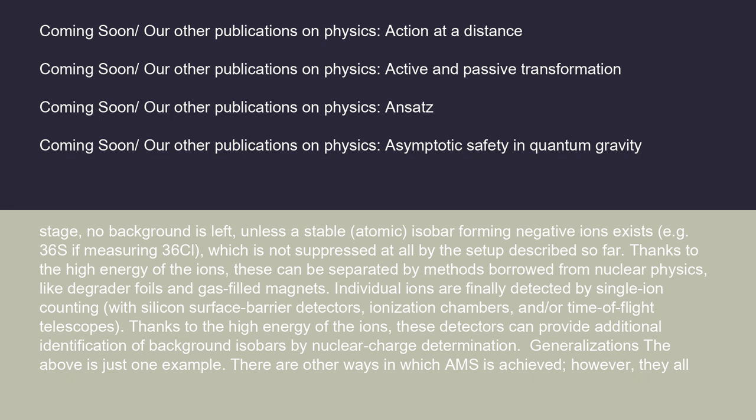After this stage, no background is left unless a stable atomic isobar-forming negative ion exists — e.g. 36S if measuring 36Cl — which is not suppressed at all by the setup described so far. The ions are finally detected by single ion counting, with silicon surface barrier detectors, ionization chambers, and/or time-of-flight telescopes.